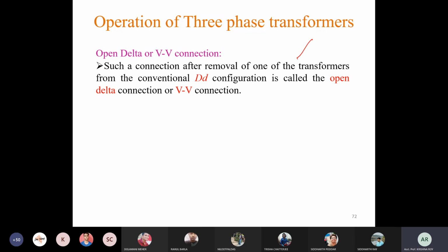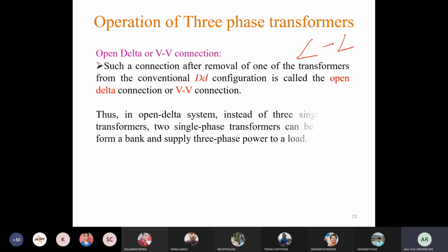Okay, so it will look like this. So this is open delta or VV connection. So in an open delta system, instead of three single phase transformers, two single phase transformers can be used to form a bank and supply three phase power to a load. See, we are using only two transformers in open delta or VV connection, but still we are capable of supplying three phase balanced load. Okay, so the three phase supply system will form with these two transformers only. That is the most interesting part of this connection.